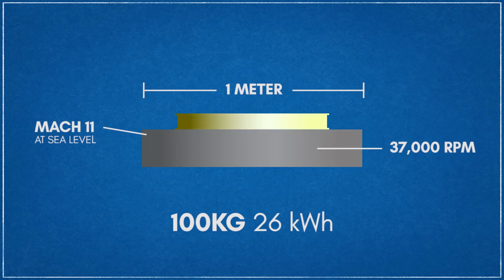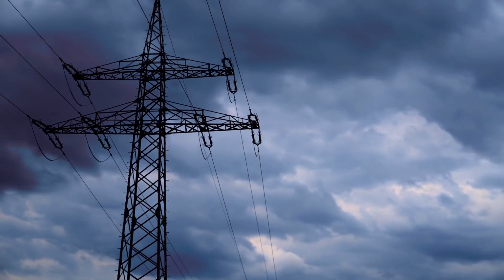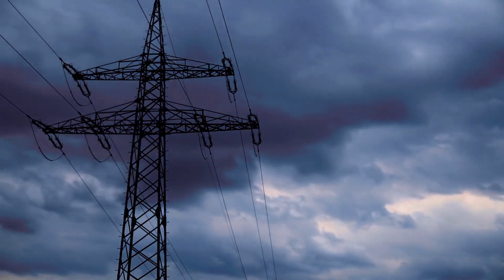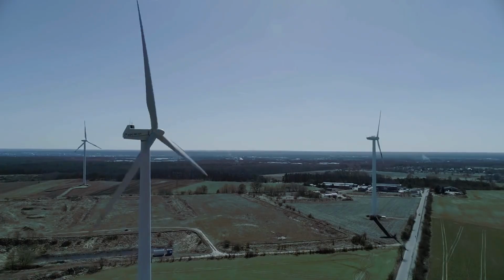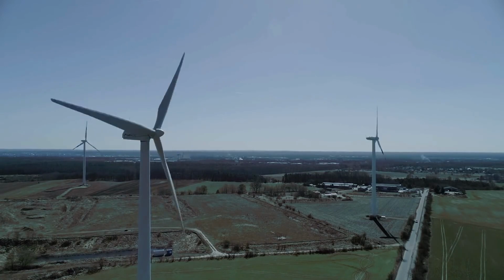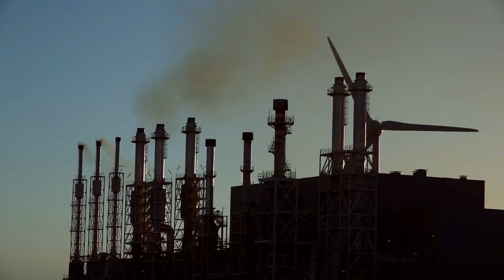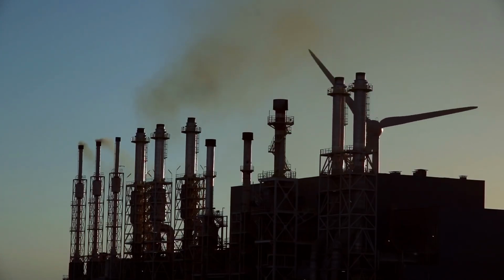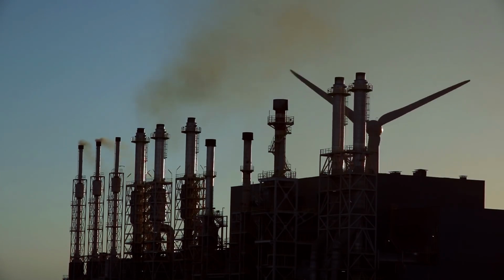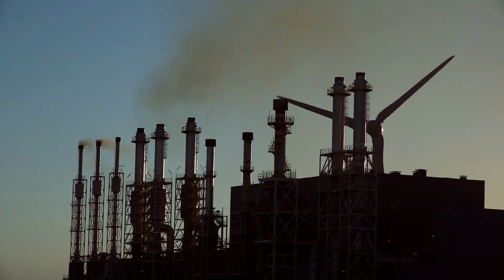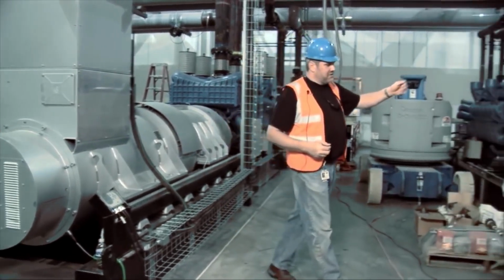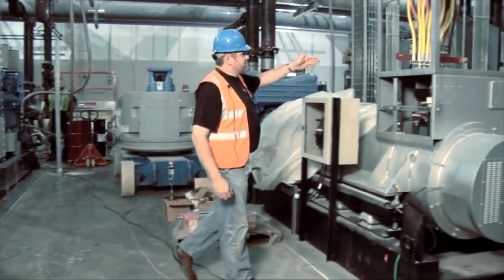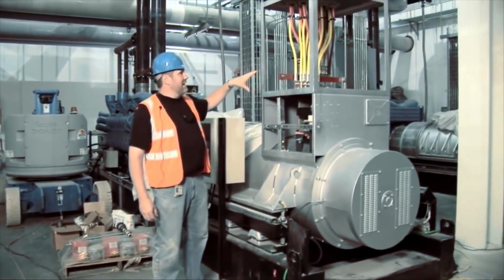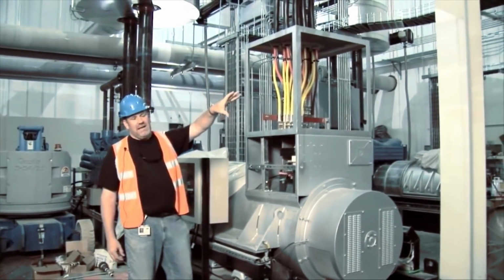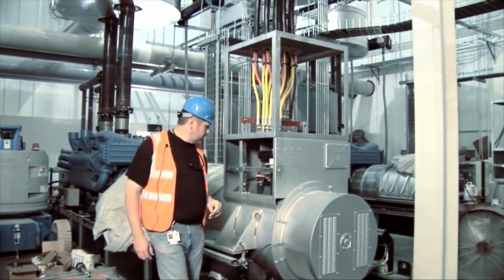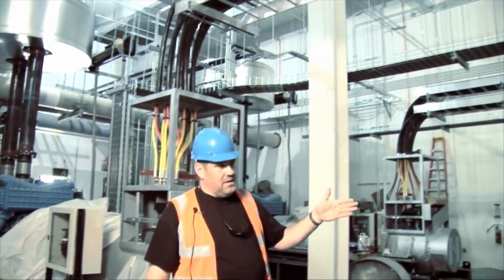batteries for similar performance. Within the limits of current technology, flywheel energy storage systems are more suitable where high bursts of power are needed for short duration. Their power density far exceeds that of chemical batteries, easily supplying hundreds of kilowatts in seconds with little or no degradation at low long-term operating costs. One of the most common uses of flywheel energy storage systems is as uninterruptible power supplies.